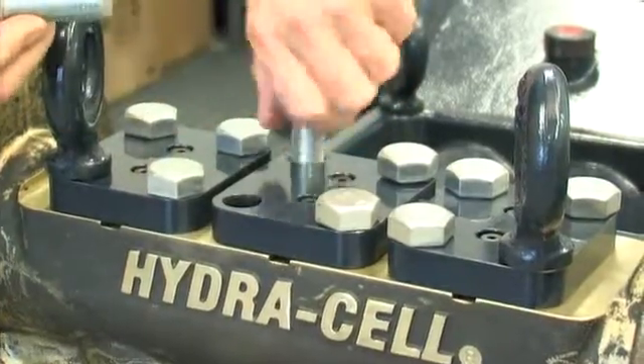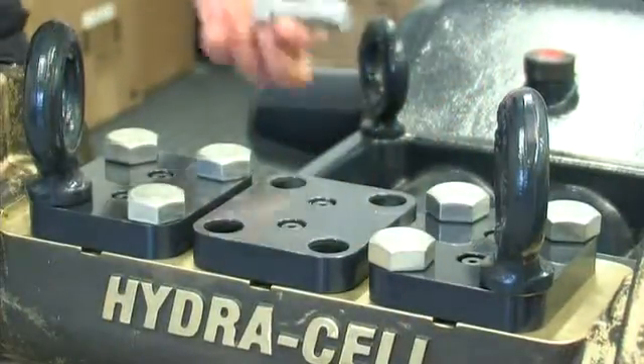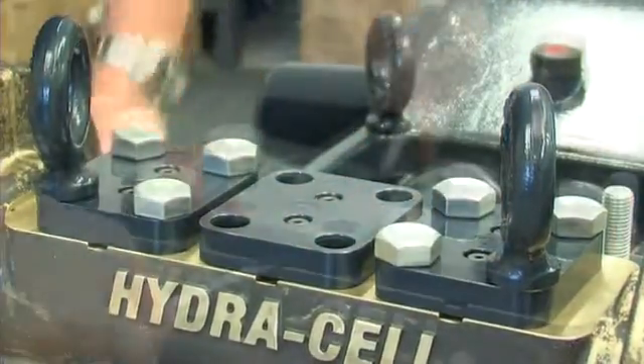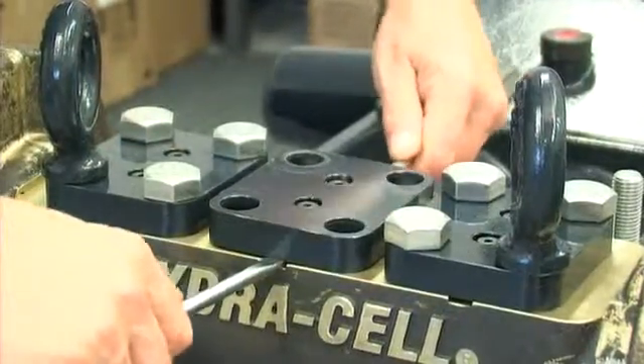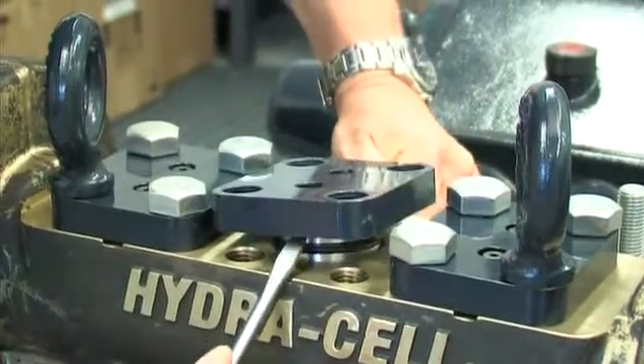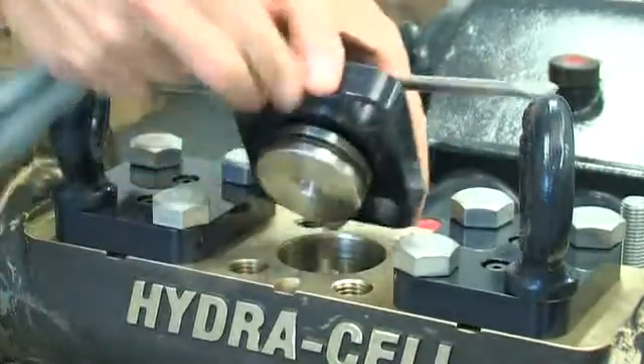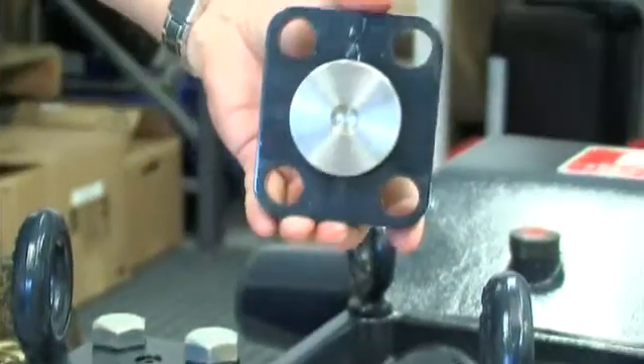Firstly, remove the four cap screws or the eyebolt and three remaining cap screws from the discharge retainer plate. The plate itself can then be removed, but it will take a little leverage to accomplish this. The retainer plate comes away complete with the outlet valve port plug and associated backup ring and O-ring.